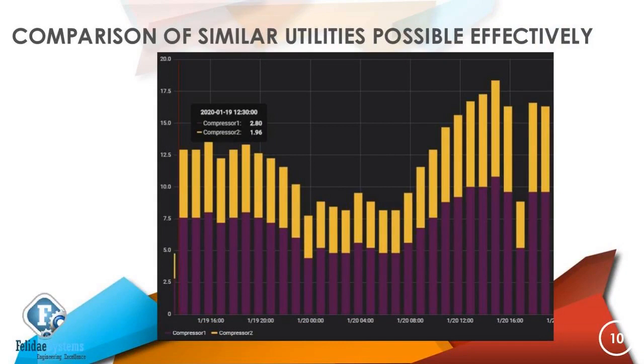This is one small case — say we have two compressors, just as an example. We should know how much energy is being consumed, and we know the CFM generated by these compressors. With this energy monitoring system, we can find out how many hours each compressor was run, and compare the energy consumption. So if we have a new generation compressor, we can optimize our process so that this one runs 75% of the time and this one runs 25% of the time.